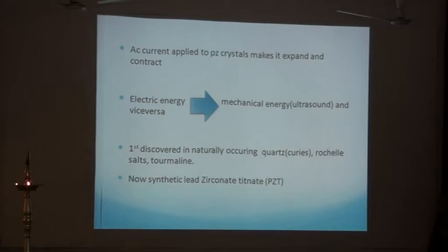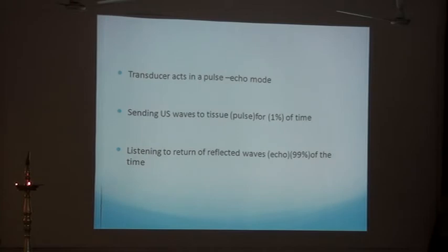This was first discovered in naturally occurring quartz by the Curies, and it is also present in Rochelle salt and tourmaline. But nowadays we use synthetic lead zirconate titanate, or PZT, crystals as the piezoelectric crystal. This transducer acts in a pulse echo mode. What is that? It means that in one cycle, only 1% of the time the transducer is sending the pulse of ultrasound waves into the tissue, and the remaining 99% of the time it is listening to the waves reflected from the tissue interface, which is known as the echo. So this is the basic mechanism of action.